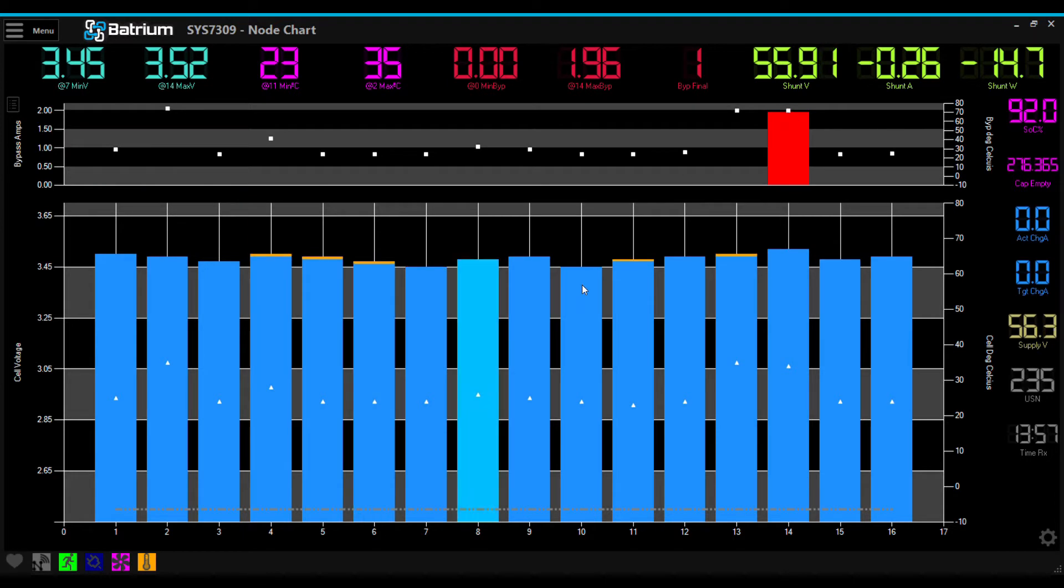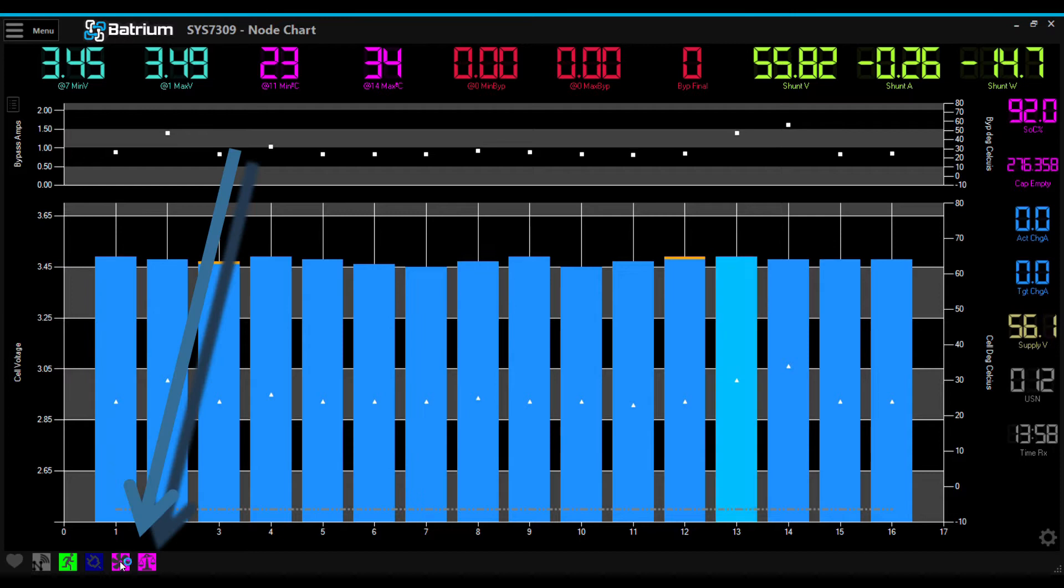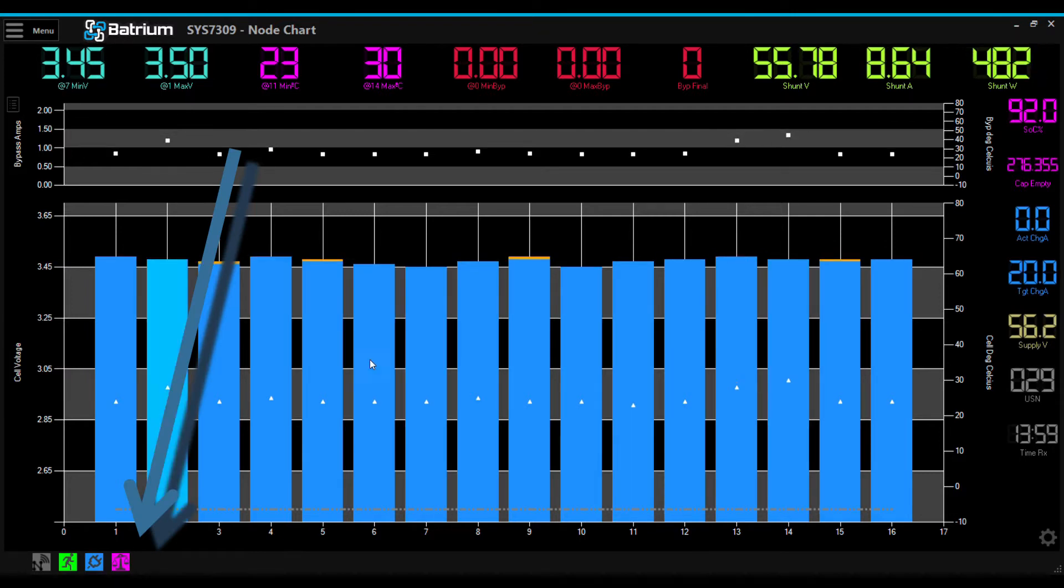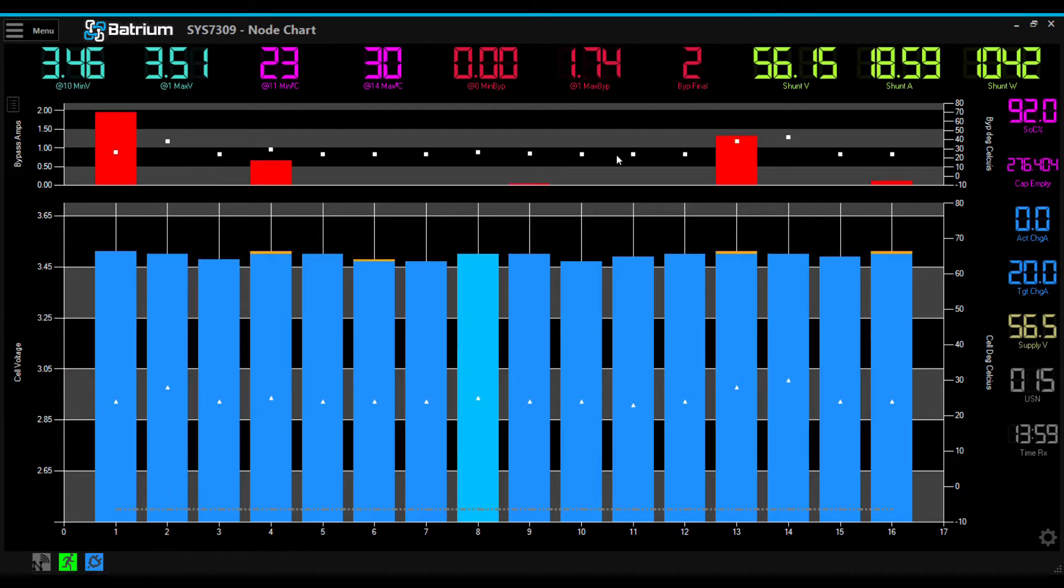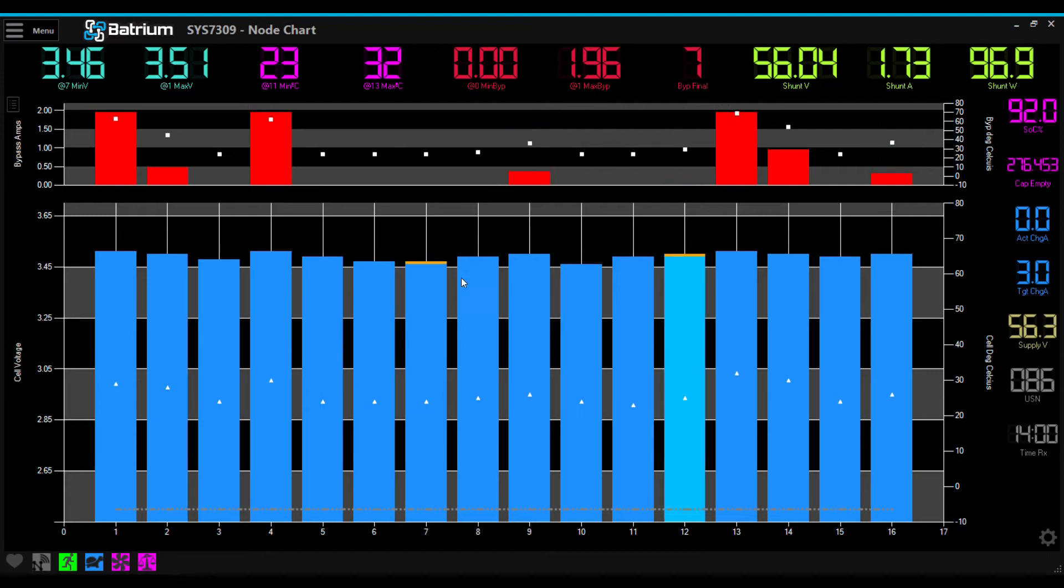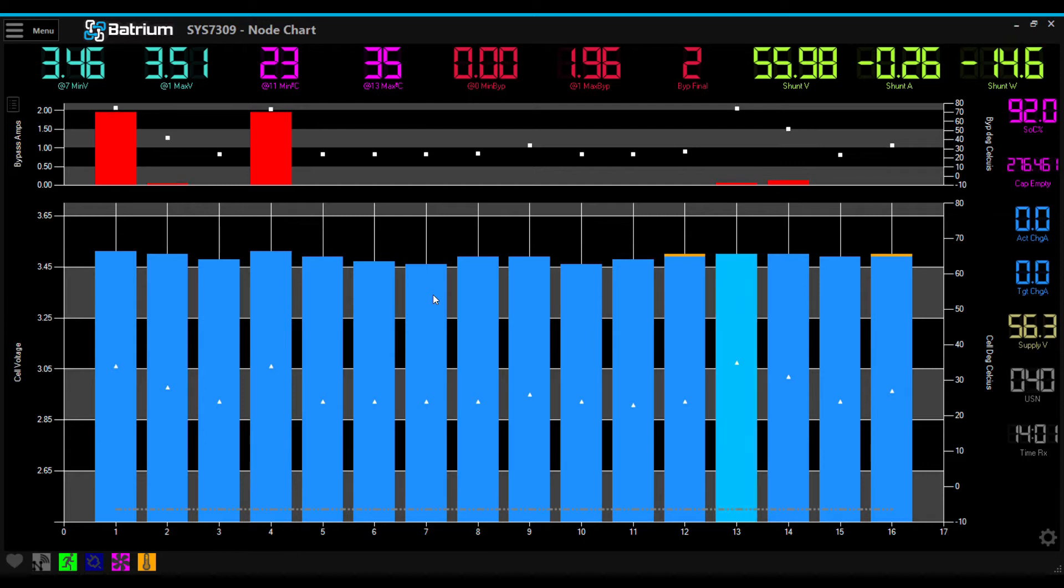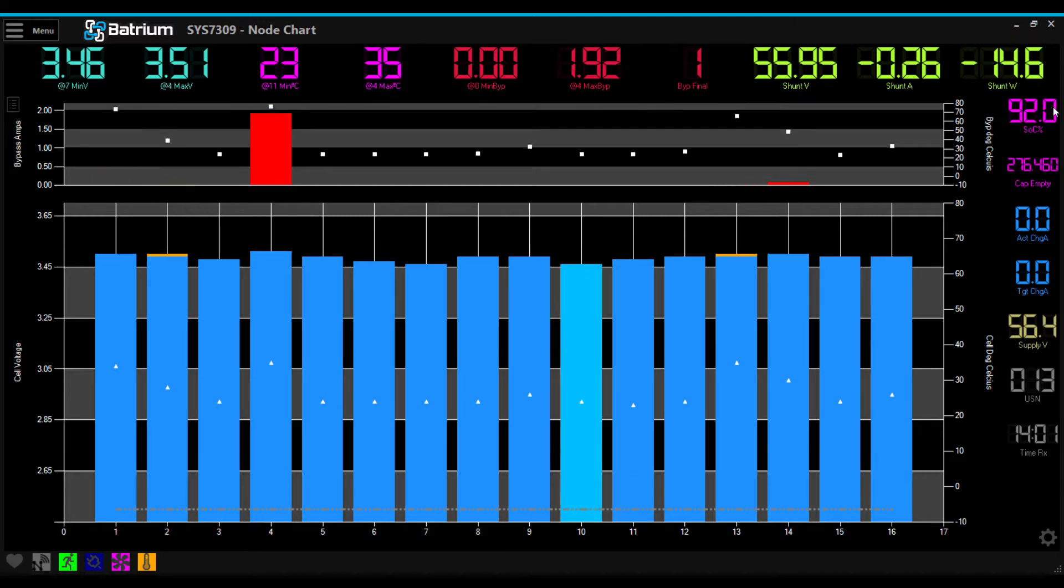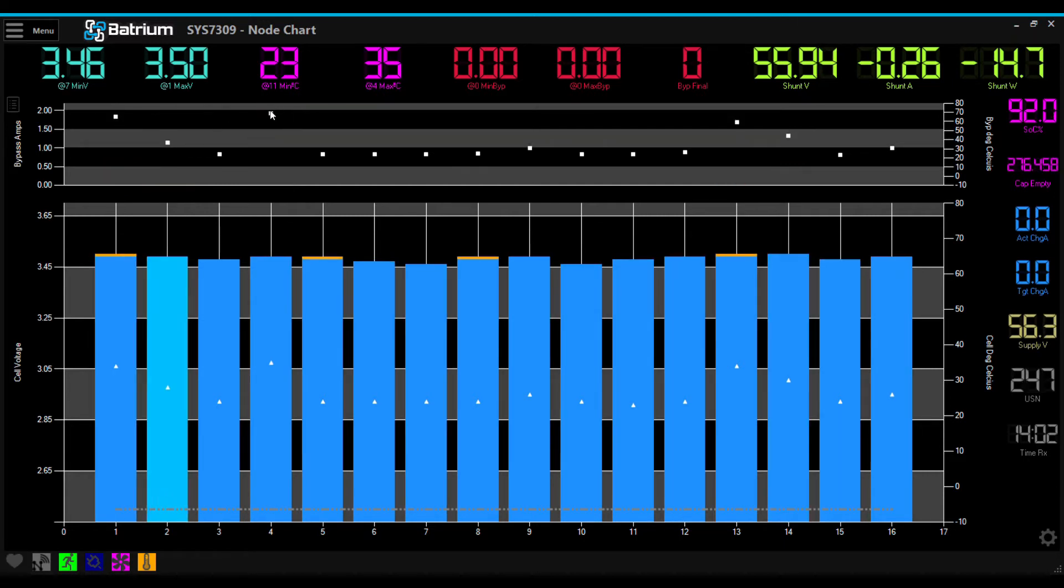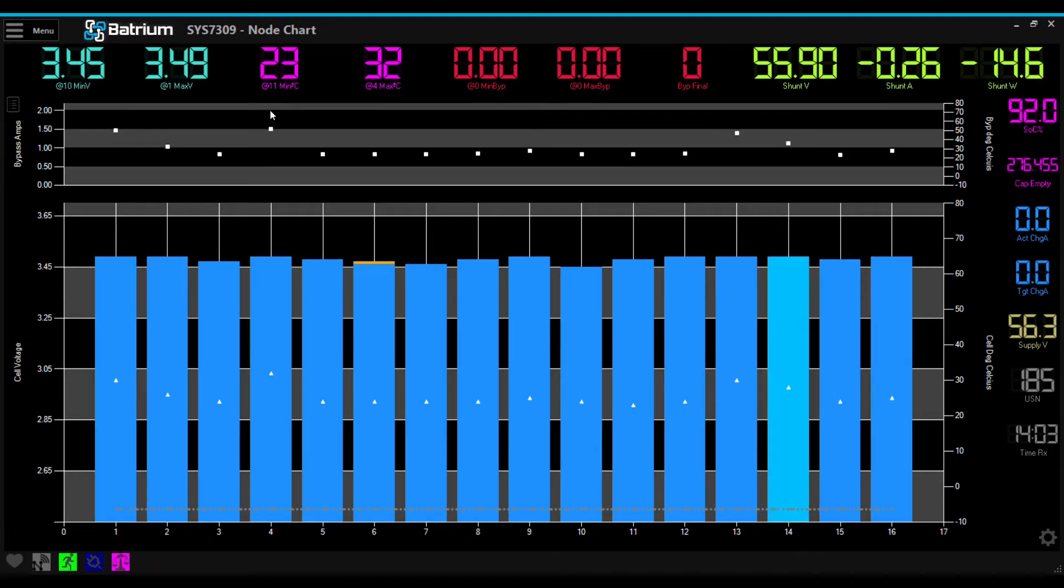The CELMON will bleed 1.9 amps from the cell, and then it will reach an over-temperature point and turn the inverter off to let the CELMONs cool down. Once the CELMONs have cooled down enough, it will start the charge process again, which will start the balancing process again, and this cycle will continue until the low cells have accepted enough charge.